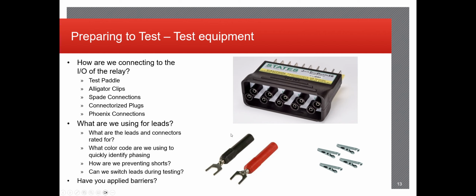We'll use color codes for testing quite often. The standard that I learned was red, white, and blue for A, B, and C phases. Those can be done for both currents and voltages. And then pretty much any other color other than those three for any outputs, inputs, other terminals.